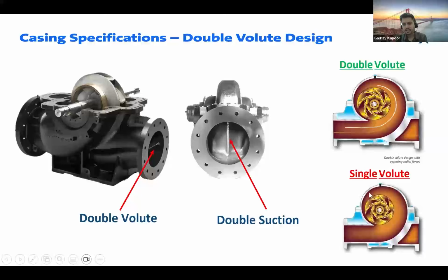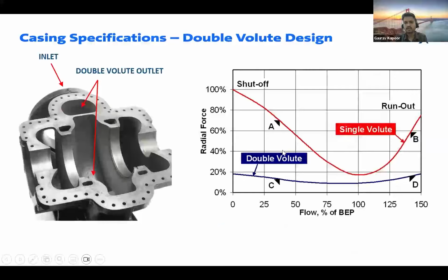Now this is single volute, where there is no metal wall in between, and this is double volute, where there is a metal casting within the casing itself. This is a very, very important point to note, because double volute design helps us reduce the radial forces drastically. So on this side, if you see a curve, the single volute forces are shown in red and double volute in blue.